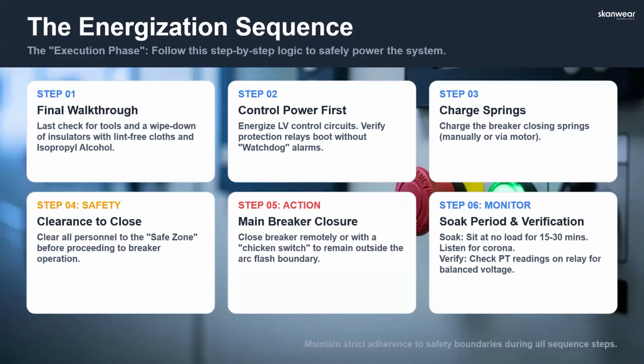So it's clear to understand when we're doing the switching, part of your planning and step-by-steps is putting your MOPs together. How are we going to be closing those breakers? Is it a manual close, or is it going to be used with chicken switches and umbilical cords? And then finally, after we do close, it's never a good process to just run right in and check everything and verify and think it's all okay. We talk about a soak period and verifying that we're listening to items. What is that soak period? And then for those technicians who do go in to check phase rotation and voltages, that they are suited in proper PPE, as we mentioned earlier.